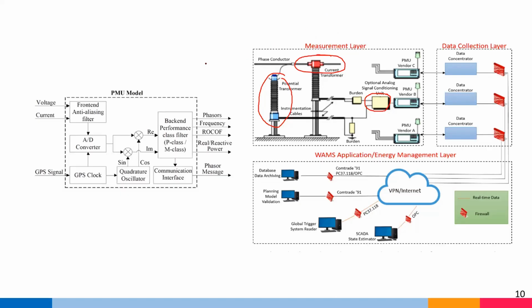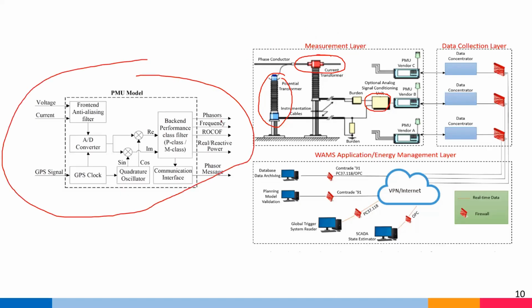So this is just the model of the PMU, and you can see it is able to provide phasor, frequency, and rate of change of frequency. If you have current and voltage phasor, you can easily calculate active and reactive power, or have some masses also, or some digital information. All this can be provided from a PMU model from the substation side.